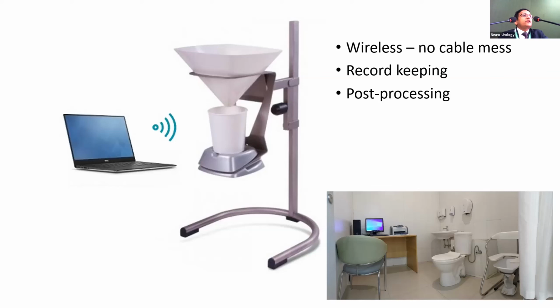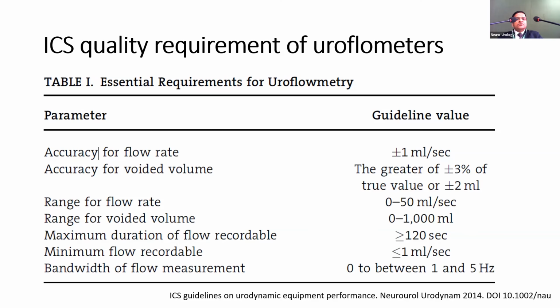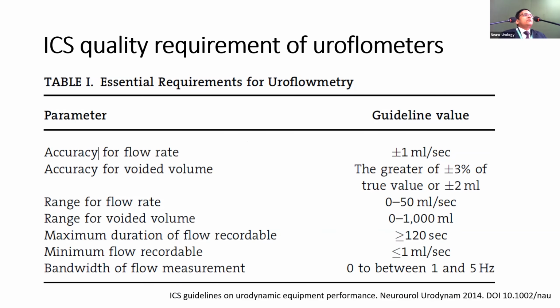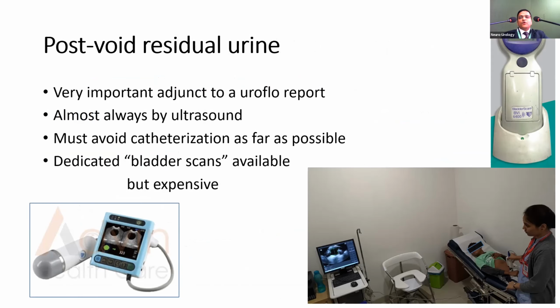So it's good for record keeping. You can post-process the data. The problem is sometimes we do face software errors while doing the test, or some Bluetooth connectivity issues, so that can lose the data. ICS has clearly defined the accuracy requirements for uroflowmetry. Flow rate should be within 1 ml per second error. The accuracy of voided volume should not be worse than 2 ml or 3%, whichever is greater. The bandwidth of flow measurement should be between 1 and 5 hertz. Now, we can buy any machine, Indian or imported, whatever our pocket selects, but it should meet these basic minimum criteria.